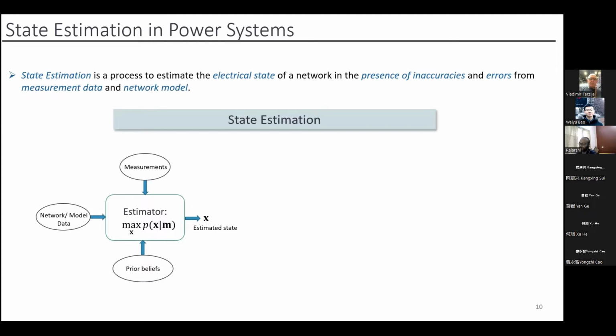This is the process of state estimation. Defined mathematically, the state estimator takes as inputs the measurements from the system, the network data such as line parameter data and topology data, and some prior belief, which is incorporated into the statistical estimation. This prior belief can relate to the nature of the noise distribution for the measurements, or to a pseudo measurement generated using historical data. So that is also a prior belief, and it gets integrated into the system.